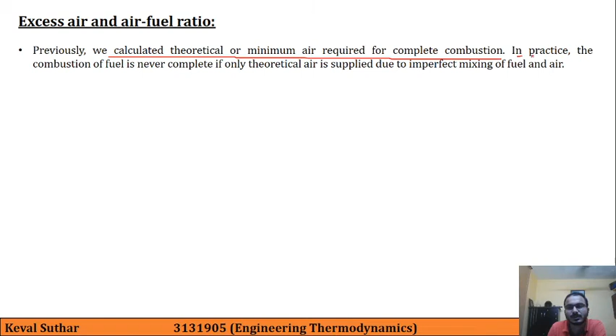So our next theory is excess air and air fuel ratio. So previously we were only calculating the theoretical or minimum air required for complete combustion. In actual practice, the combustion of fuel is never complete if only theoretical air is supplied. Why? Because there will always be incomplete mixing of air and fuel. That is, the theoretical value or minimum air requirement is not sufficient for complete combustion. So to ensure complete combustion of fuel, usually actual air is more than the theoretical air required, so we need to provide some excess air. The difference between actual air supplied and the minimum air, that is stoichiometric air required for complete combustion, is known as excess air.